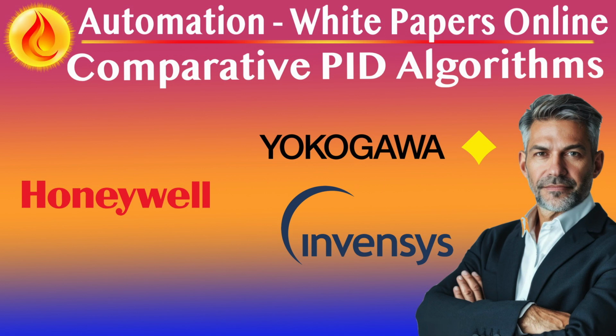Integral action, reset behavior, and anti-windup. Honeywell's controllers come with integrated anti-reset windup, ARW, logic and external reset feedback, RF, built into the PID block. This ensures consistent behavior when control outputs hit actuator limits and allows smooth handovers during mode transitions. It's particularly useful in cascade and override architectures, where nested controllers need coordinated reset behavior.